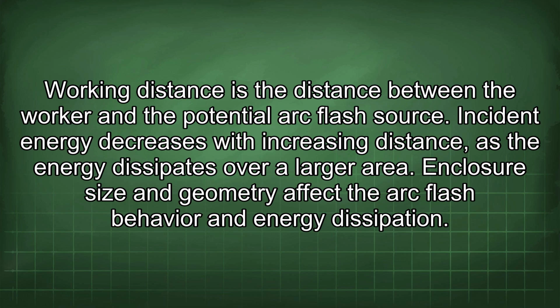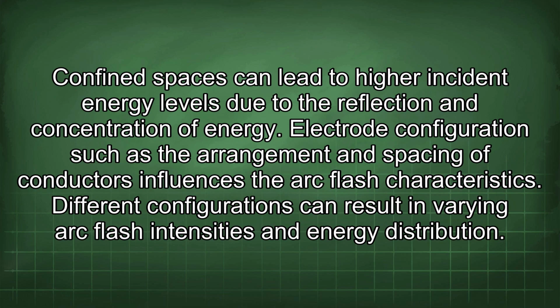Working distance is the distance between the worker and the potential arc flash source. Incident energy decreases with increasing distance as the energy dissipates over a larger area. Enclosure size and geometry affect the arc flash behavior and energy dissipation. Confined spaces can lead to high incident energy levels due to the reflection and concentration of energy.